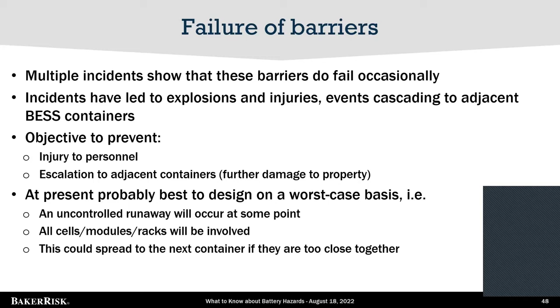I think you have to consider that the risk is that an uncontrolled thermal runaway event will occur at some point. And if that happens, if you're trying to think about your maximum loss or worst case, you need to assume that all the racks in the container or the enclosure will be involved. And if those containers or modules are too close to each other, it could propagate to one other container.